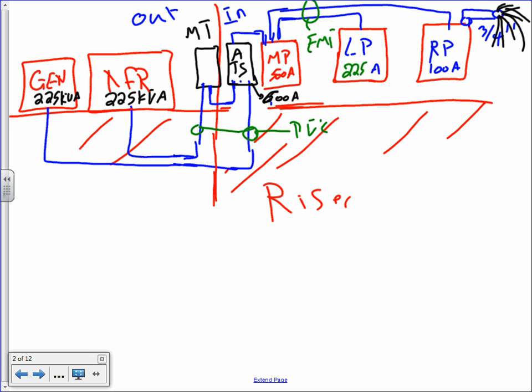Now, what this exercise is about, guys, is taking a 3/4 inch EMT conduit from here and filling it with wires from the receptacle panel or the lighting panel and feed the branch circuit. So that's what I'm going to talk next about, the branch circuits. I want to remind you, everything above ground is going to be what type of conduit? EMT. Everything below ground is going to be what type of conduit? PVC. Okay?